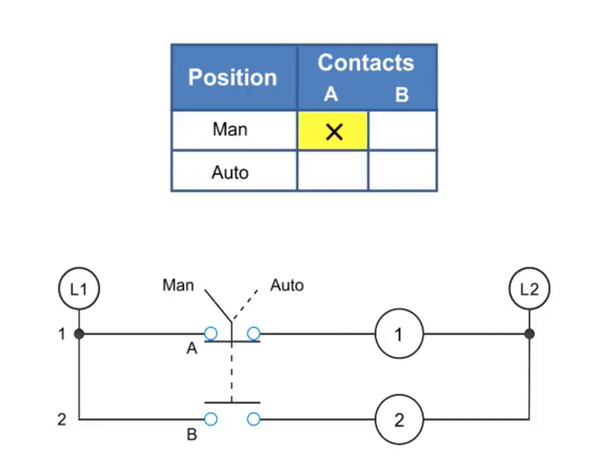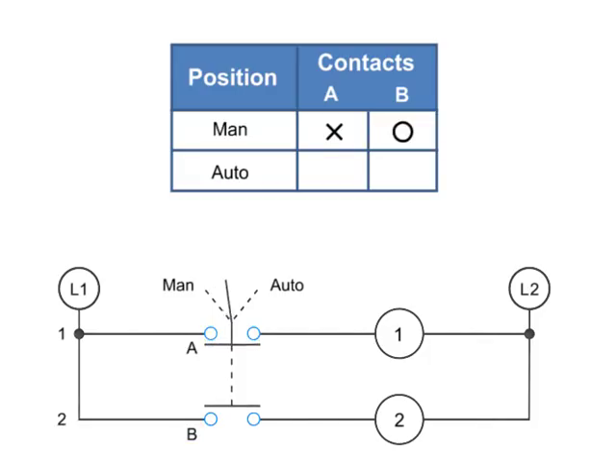An X is placed in the table if a contact is closed in any position. An O is used to depict that a contact is open. Thus, if the selector switch is in the MAN position, A is X or closed and B is O or open. When the switch position is set to AUTO, A is O or open and B is X or closed.